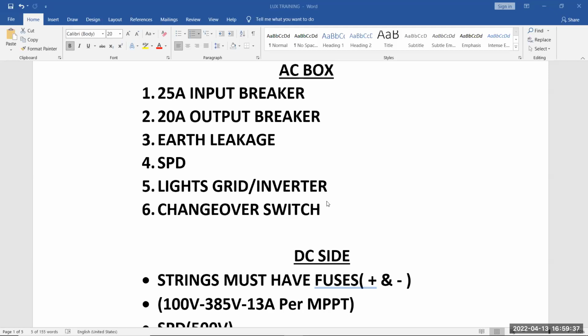Now, the reason for the 25 amp input breaker is you'll see this inverter has the capability to pass through the current. So that means if you pull more than 5 kilowatt out of it, it will switch to Eskom and all that current will run through the inverter to the house. So you can put 6.5 kilowatt through this inverter without tripping the inverter if Eskom is there, but then you'll have a pass-through current of 6.5 kilowatts through my machines. Now, this machine isn't designed to do that. It will allow it, but if you keep on running that type of amount of power through my inverters, it won't have the lifespan that you would expect from it. So that's why we put a 25 amp input breaker, so that we can just protect the system there as well. If you go over that amount, it will trip and your inverter will still be on the safer side of life.